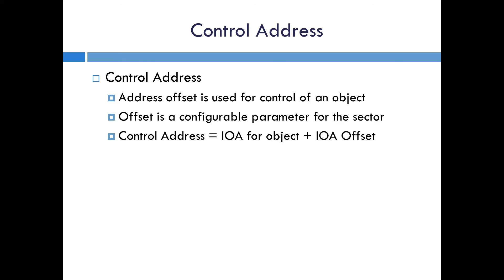The control address specifies the particular ASDU being controlled. Note that the point being controlled and the monitored point that reads back that the control happened will have different addresses. This is handled in the Triangle Microworks test harness by defining an offset between the control point and the monitored point. In the sample database we use a fixed offset between the control object and the monitored object, though that's not required by the specification. The only requirement is that the two addresses have to be unique — for example you could have control point 7 and monitor point 102. They just have to be different, not necessarily a fixed offset.